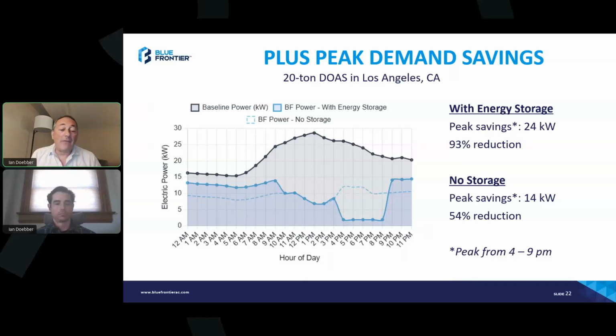So how does it look on a graph? On a 24-hour hot summer day, in gray is the baseline and in blue is the Blue Frontier unit. You can see between the hours of 4 and 9 in this example, these are the on-peak hours, the most expensive. The unit will continue to provide comfort to a space without using as much electricity. The dotted line is the same Blue Frontier unit working without a storage strategy. So two things: the delta in terms of kilowatts, but also, looking at the gray area versus the blue area, that represents the savings in energy consumption, about 54% in this case.